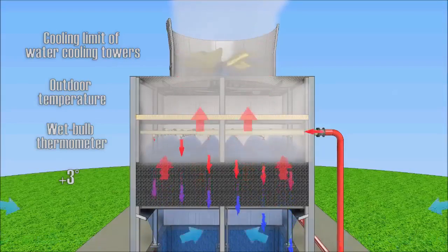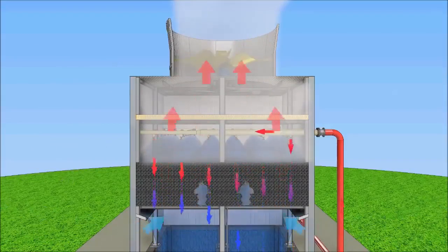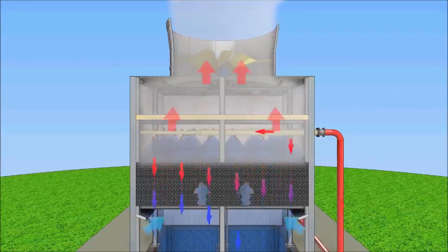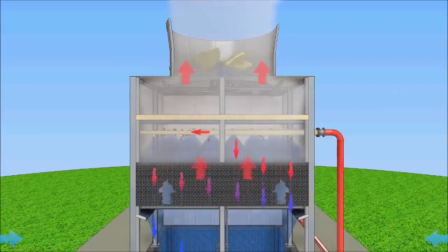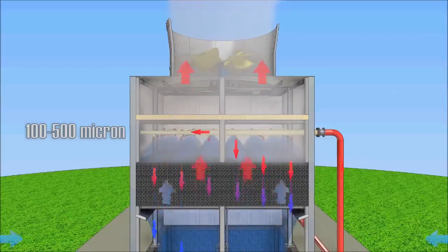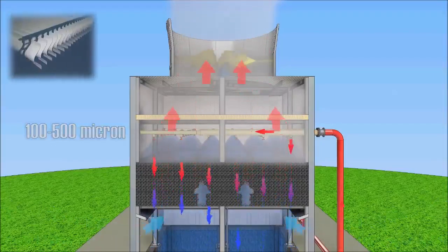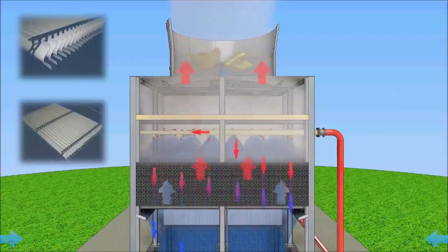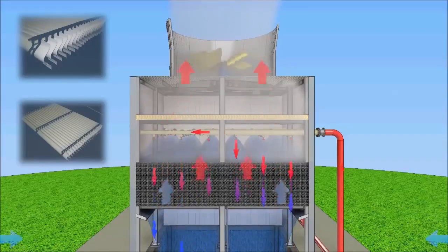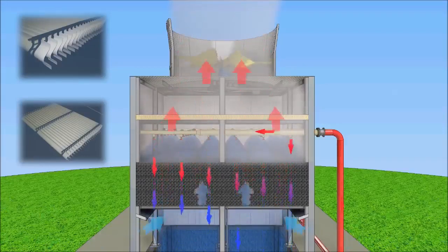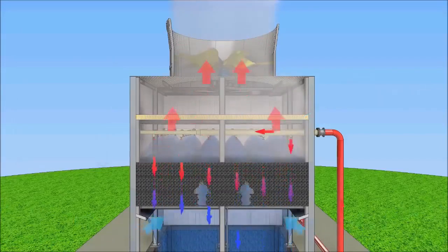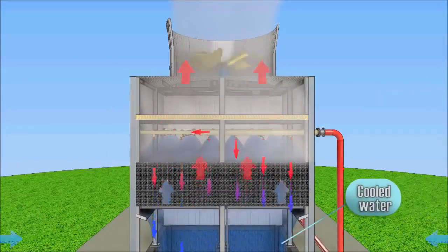In practice, the limit of cooling is the wet bulb temperature plus 3 degrees Celsius. Operating a cooling tower emits air saturated with water vapor and containing water droplets with a size of 100–500 microns. To prevent entrainment of water droplets, a drift eliminator is installed above the water distribution system.